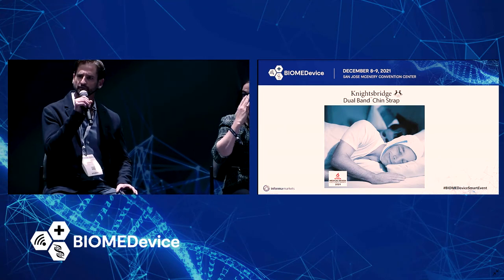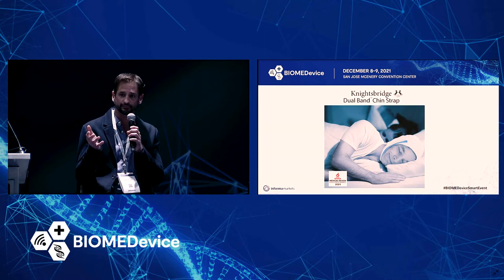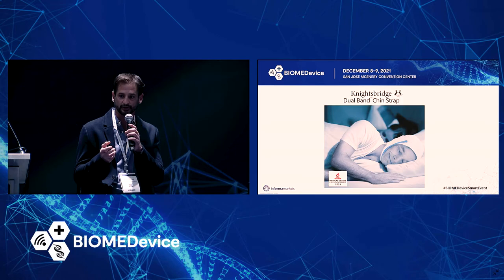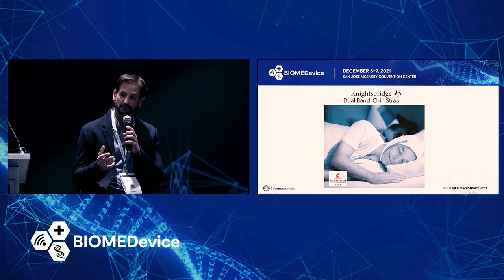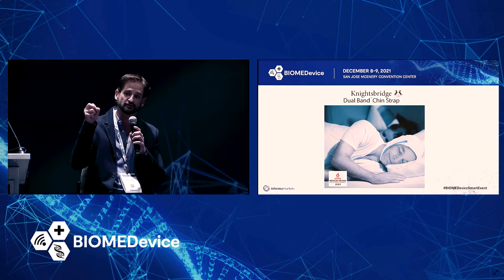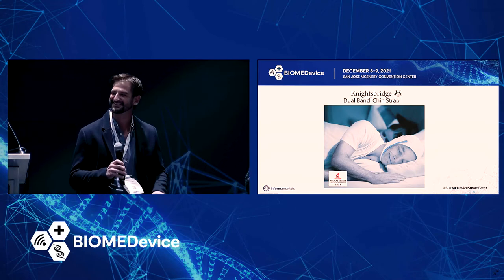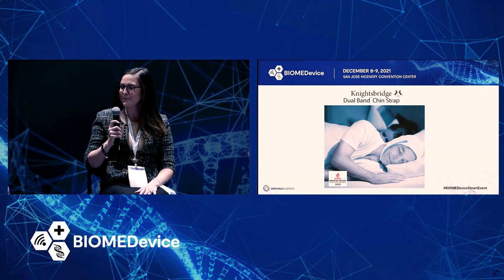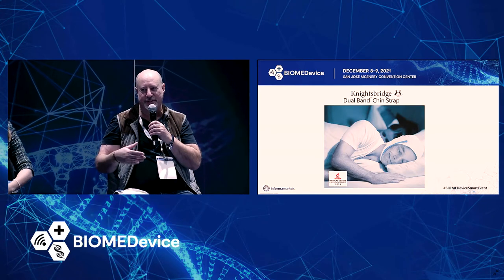Yeah, it's a really good question. I would say you have to start somewhere. Rapid prototyping is really nice. If you're doing a delivery system, something ergonomical, start with your base — start with whatever that overall device form is — and then see if you can use it and what you need to do with it. When I can't get started, I think in my head: what does it look like? Just make what it looks like. Make just a dummy, then add things to it as you go — like clay. With software, we tend to use something as simple as PowerPoint, showing potential screens to end users to get their input. I would just say: start with the hardest stuff first — if you can't solve the hardest issues, you might as well know that right away.